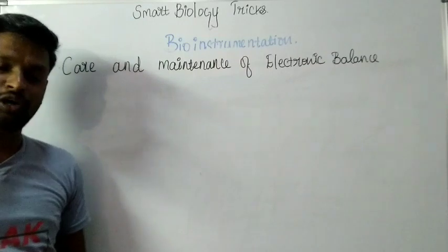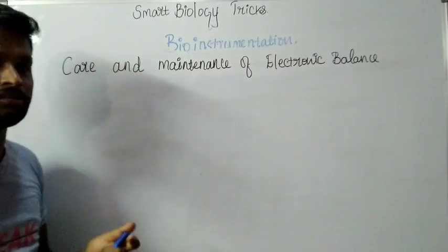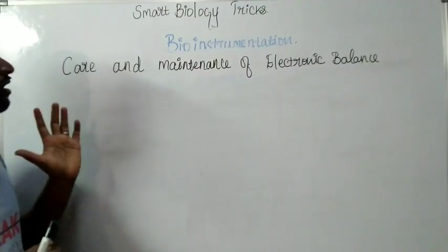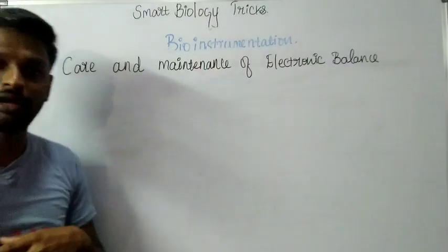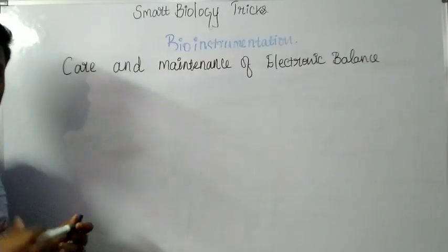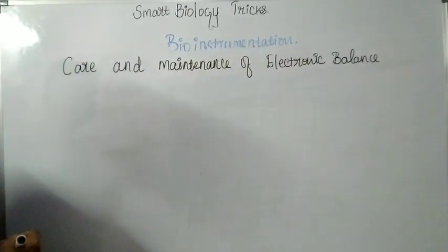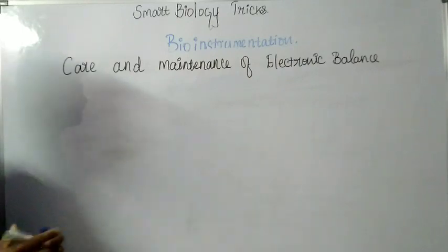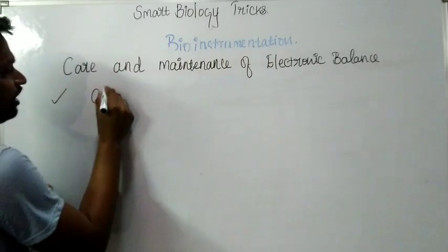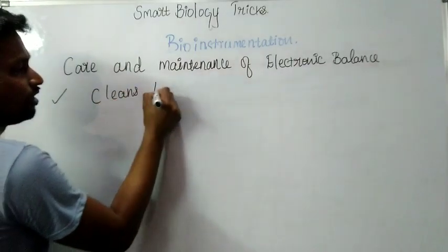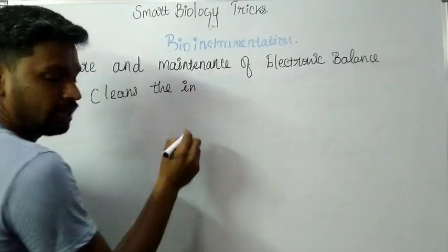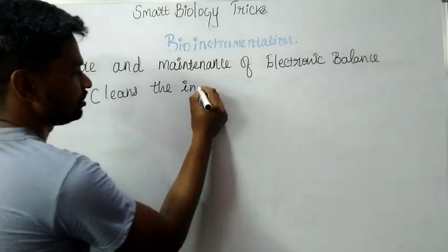As discussed in our online class, the electronic balance is a sensitive instrument, so we should take care of the instrument while in usage. Okay. So we will see one by one the maintenance, how to care for the instrument, how to maintain the instrument in our laboratory. So we should clean the instrument each and every time of usage.